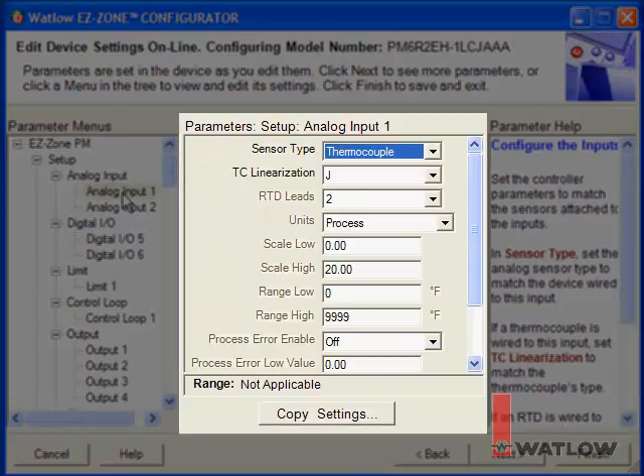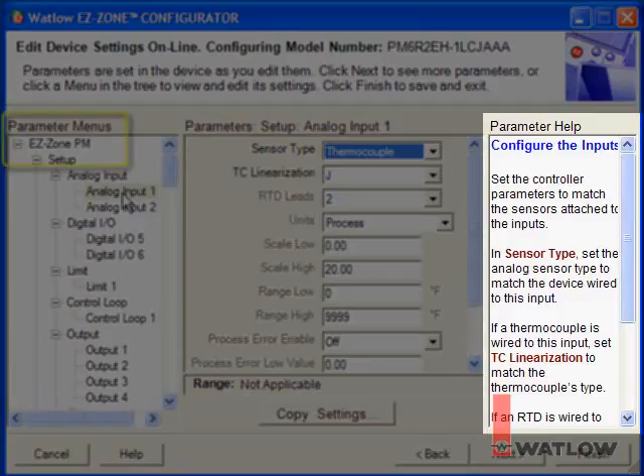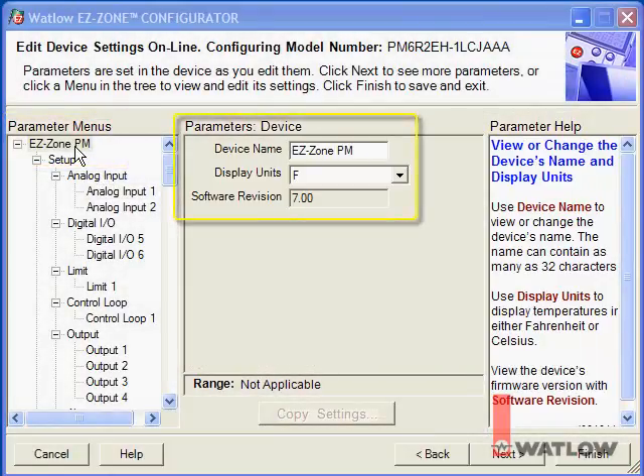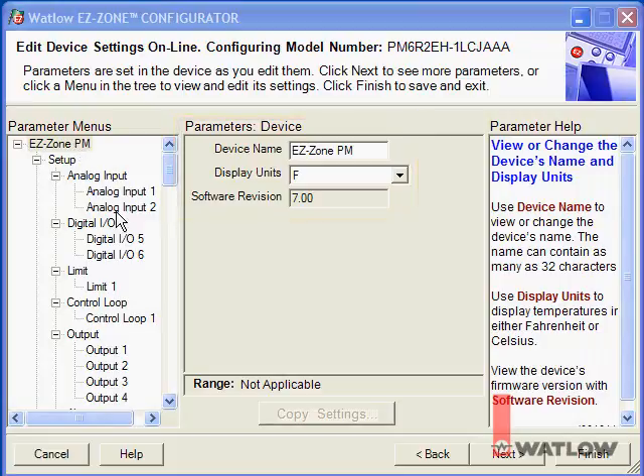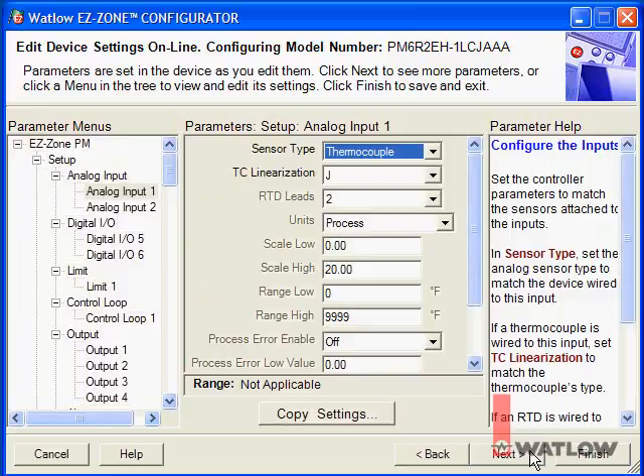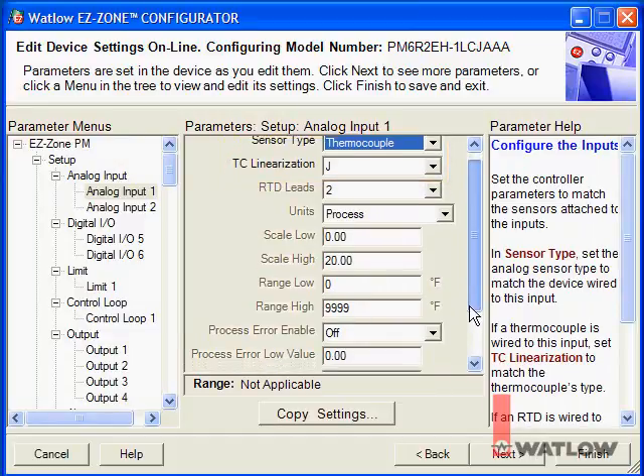The Parameter Help window displays help for the currently selected parameter. The first set of parameters allows you to name the controller and choose the temperature units; it also displays the controller's firmware version. Click Next to go to the next menu. On the Analog Input 1 menu, set the controller for the sensor you have connected. In this application we're using a Type-J thermocouple, so no changes are needed.